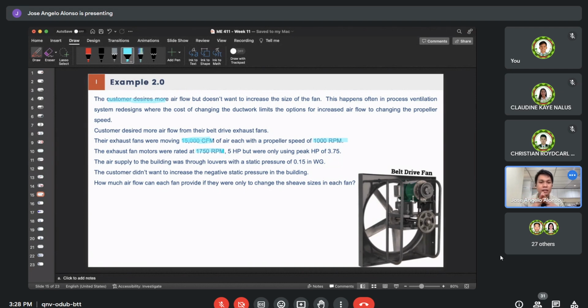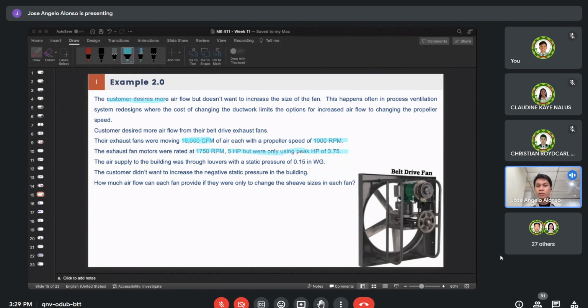It was given here as well that our motor is rated at 5 HP, but its peak is only 3.75. What does that mean? Even though the motor is rated at around 5 horsepower, the power consumption, or the peak of our motor, is only around 3.75 HP. Meaning there is still 25%, or around 1.25 HP, that is not utilized by our fan. Our motor has 25% capacity that is not being used, because only up to 3.75 is used during operation.